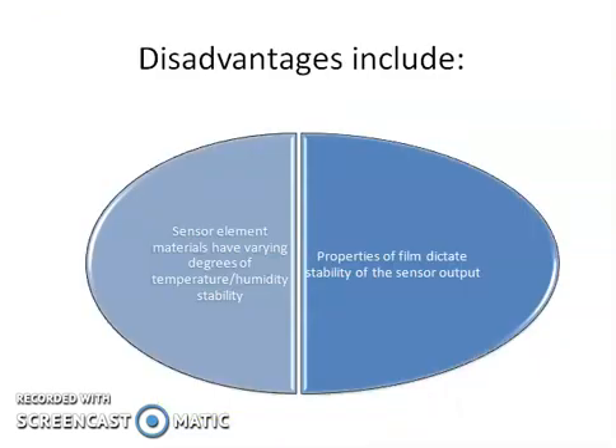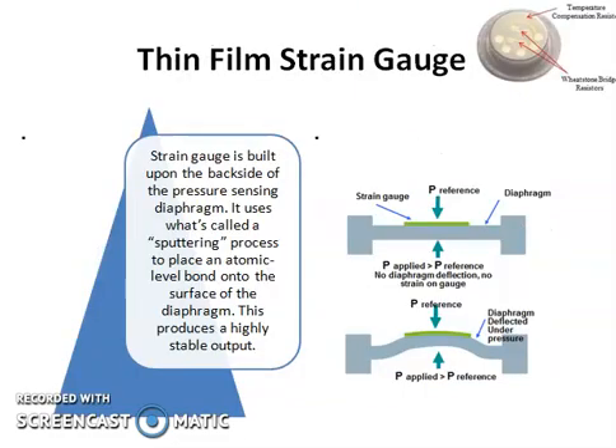And the disadvantages include that the sensor element materials have varying degrees of temperature and humidity stability, and the properties of the film dictate the stability of the sensor output. And this is the main working principle of the thin film strain gauge, which is a resistive pressure transducer.